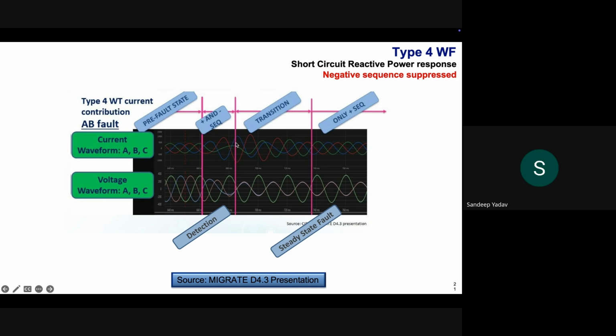Now, as soon as the converter detects that there has been a fault and the current control of the inverter kicks in, we will see that the controller will try to suppress the negative sequence current. From this second pink line to the third pink line, this is the transient transition state, from where the converter will try to suppress the negative sequence, and it will only supply positive sequence current. So for a phase-to-phase fault, after a few cycles, we see that the inverter-based resources only supply positive sequence current.